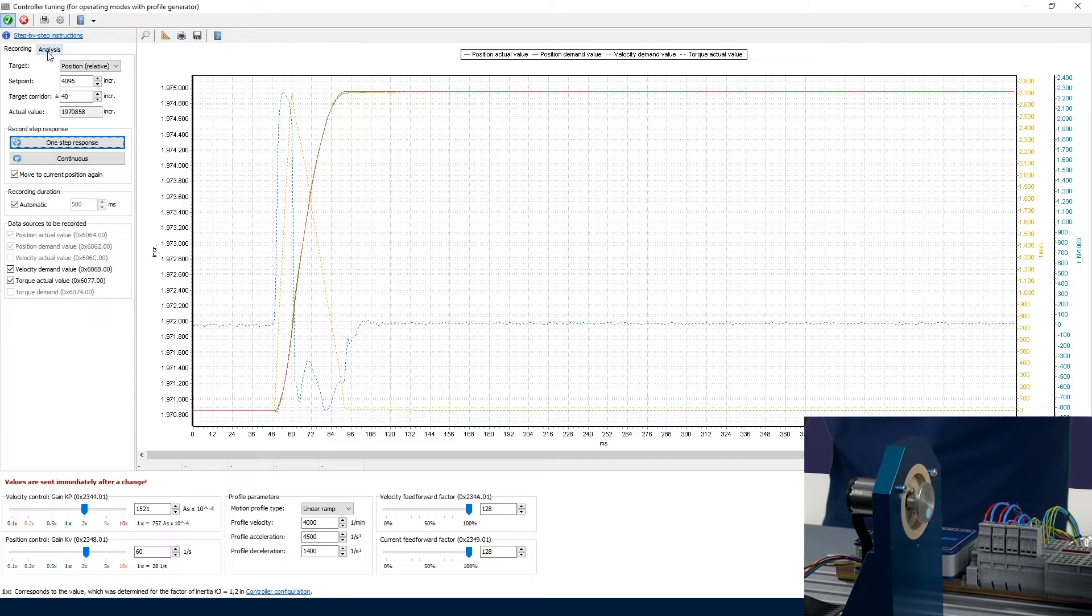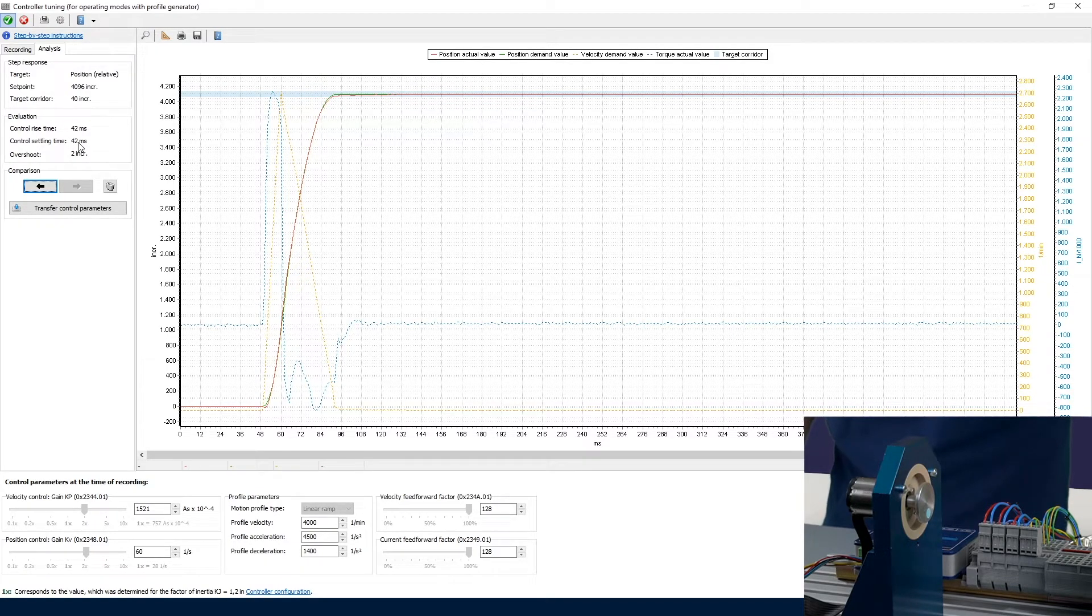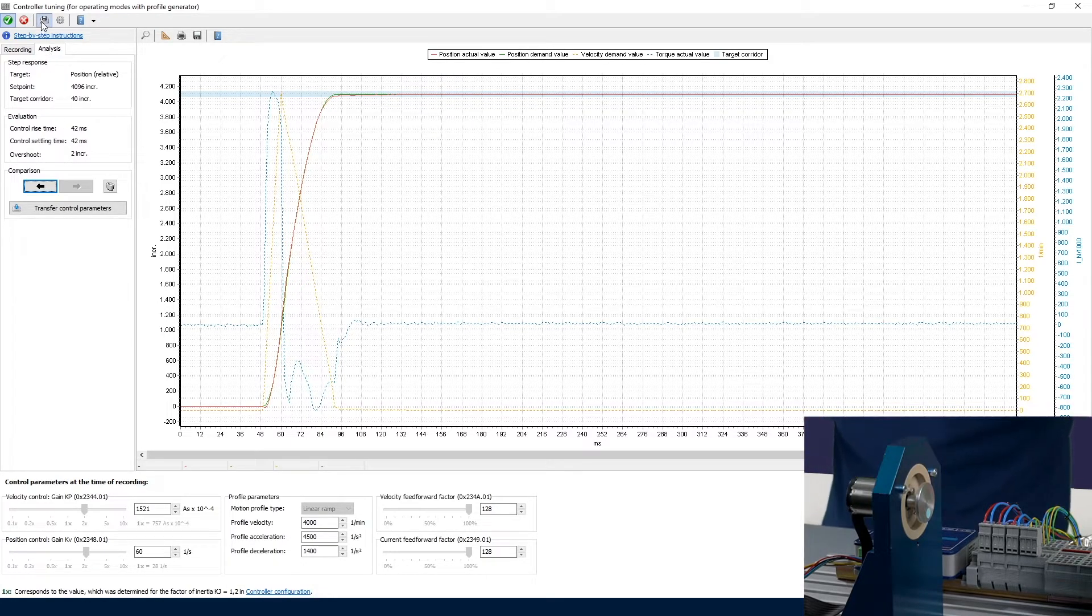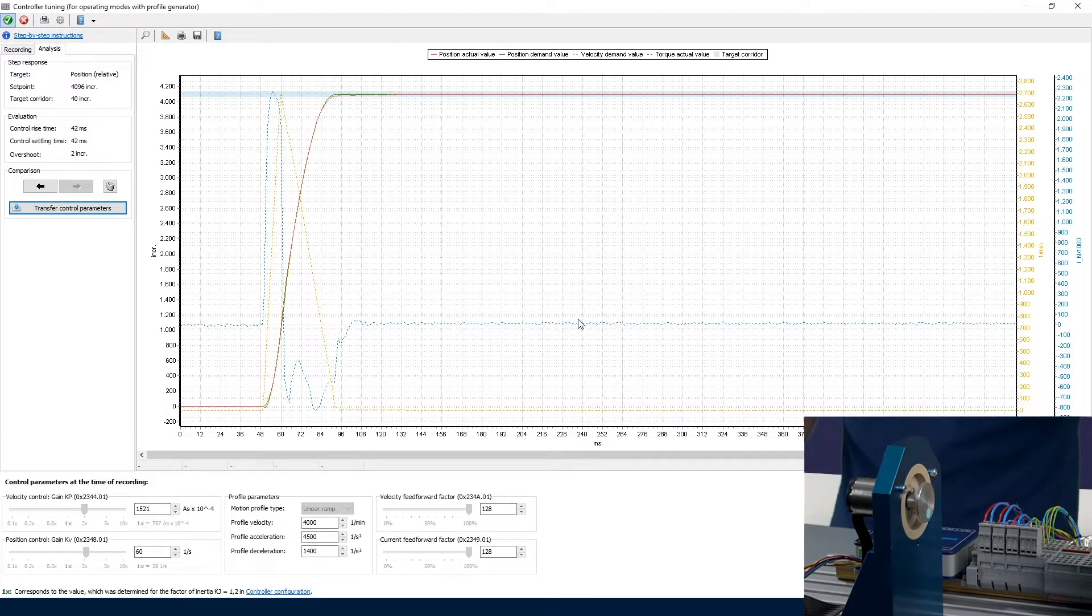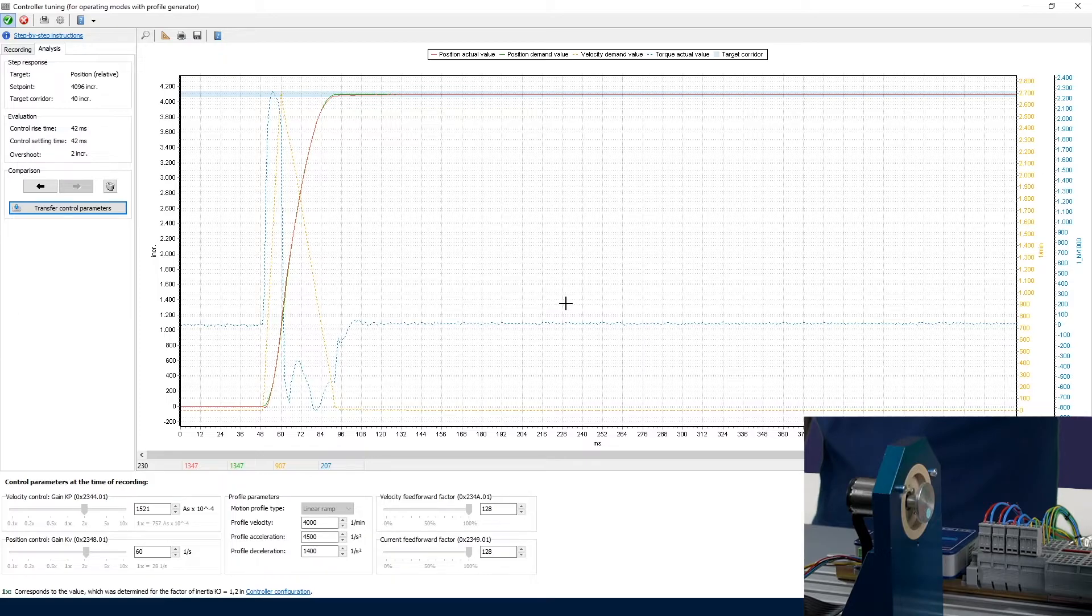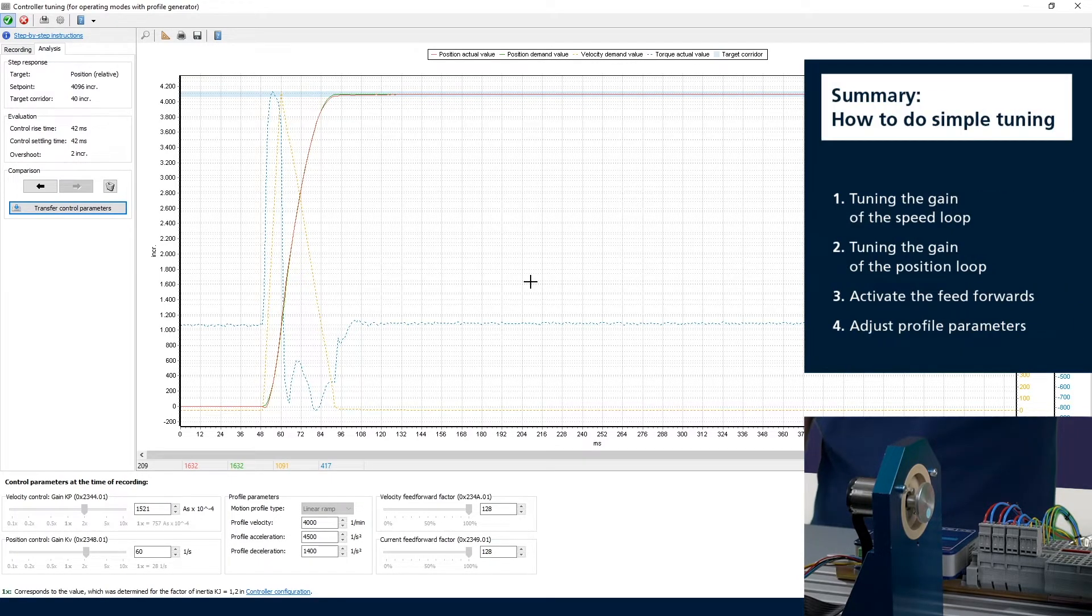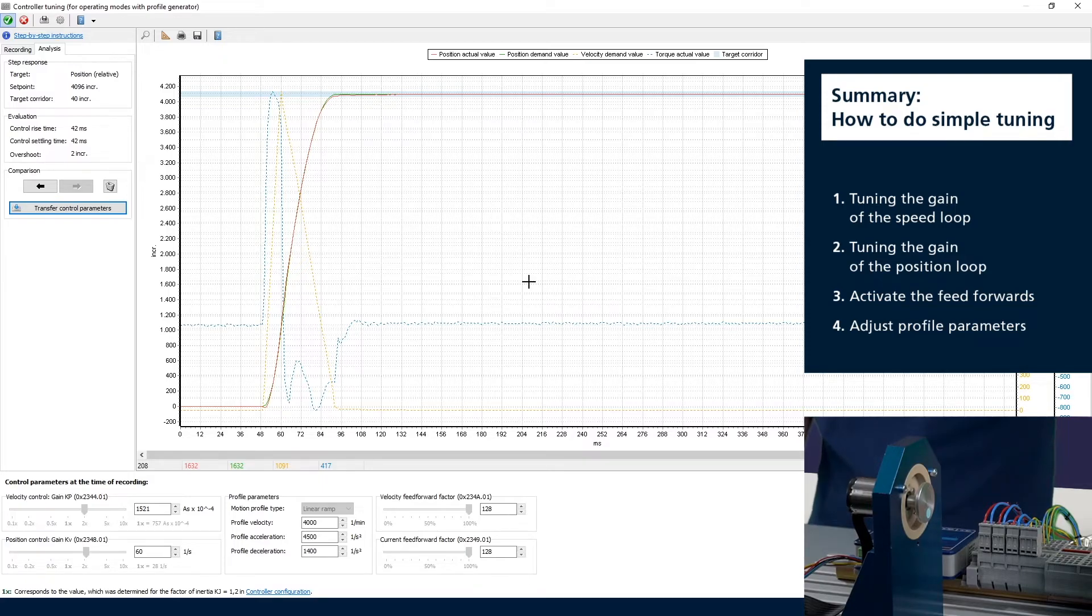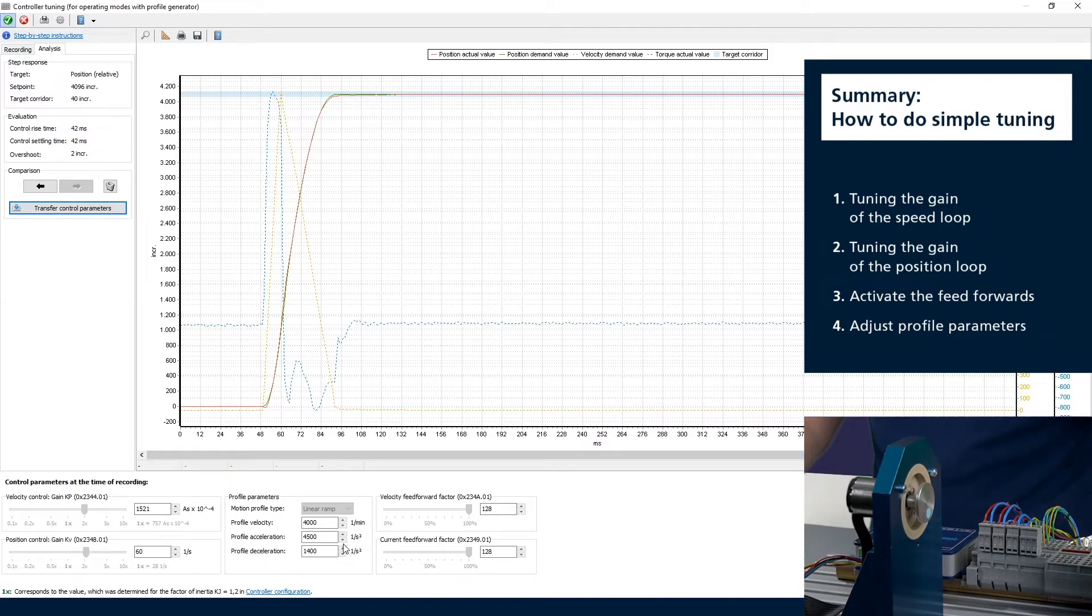I can even check with the analysis page and analyze how fast we have been and how much overshoot we had. But now I could usually start by, well, first step might be to actually transfer these parameters and maybe save them in the driver, but then connect it to whatever master you're going to use and really start working in your application. Of course we could now once again step back to the drive functions window and configure limit switches or whatever analog reference you want to have, but that's a different story. So what we did here was tuning the gains, first of the speed loop and then the position loop, with in between activating the feed forwards to get perfect following. Please be aware the local profile generator is active in profile position mode or profile velocity mode only. If your master uses one of the cyclic modes, make sure the appropriate profile parameters, so the values down here, are really set in your NC kernel in your application too.